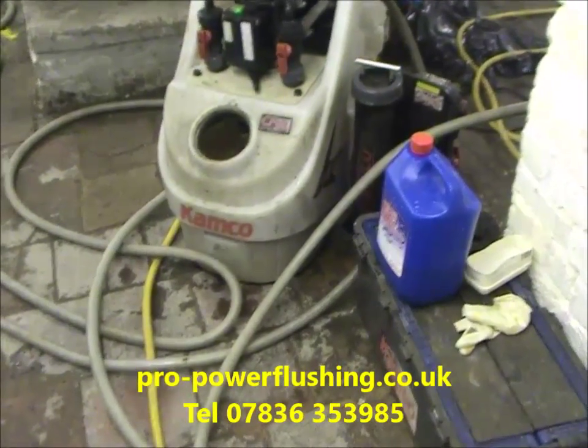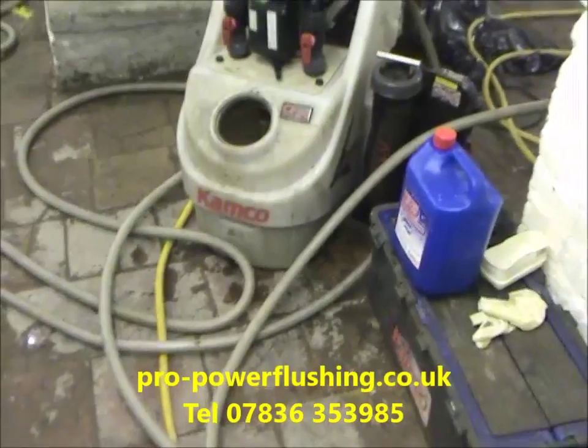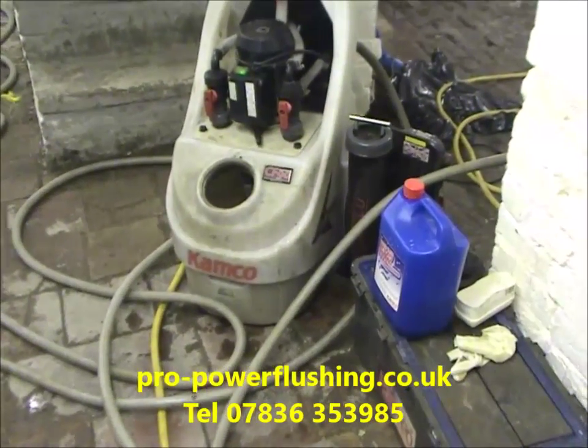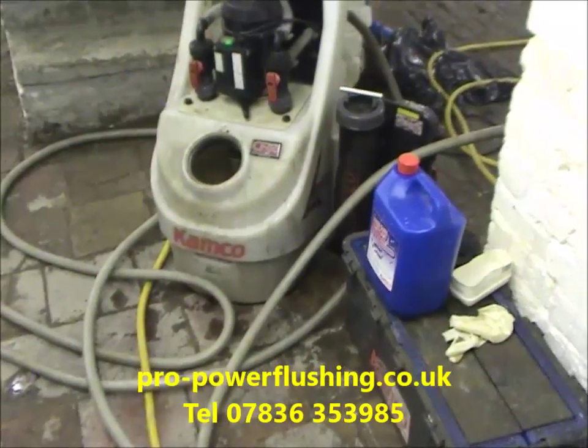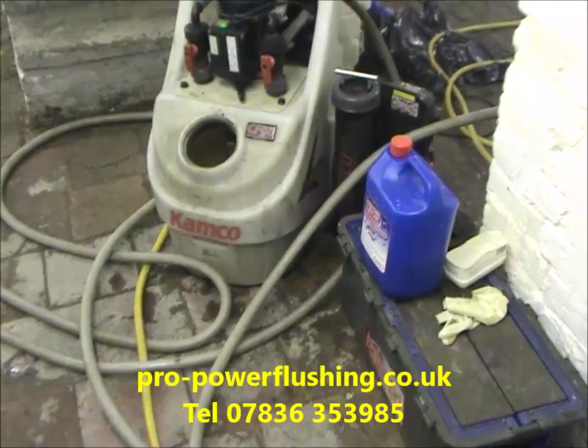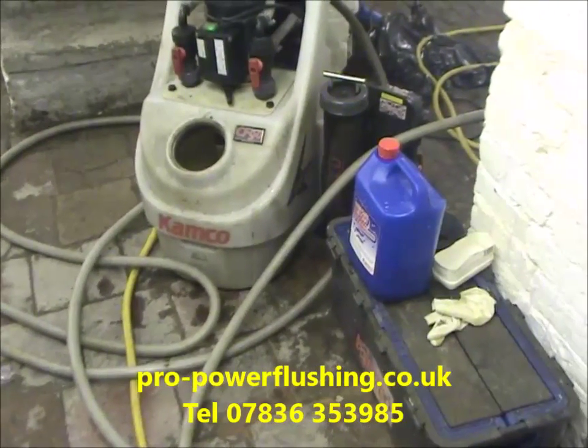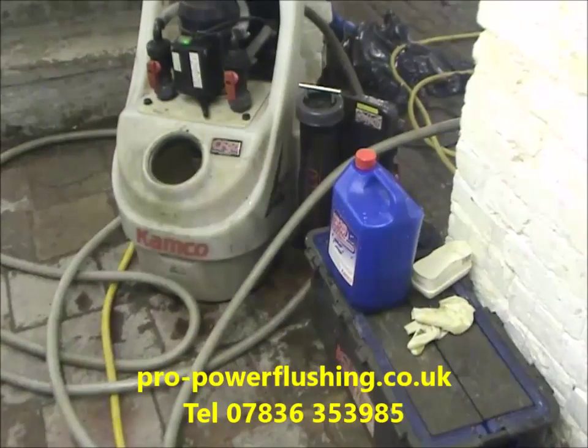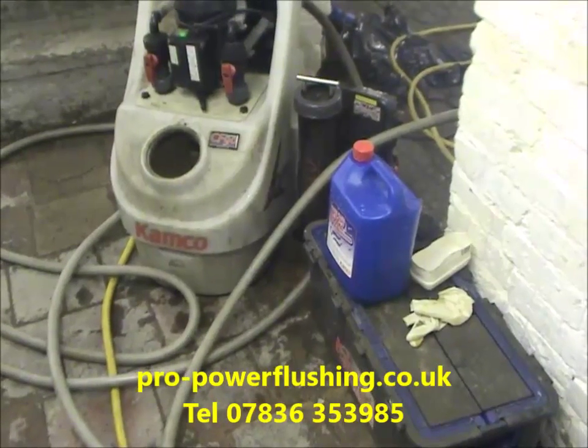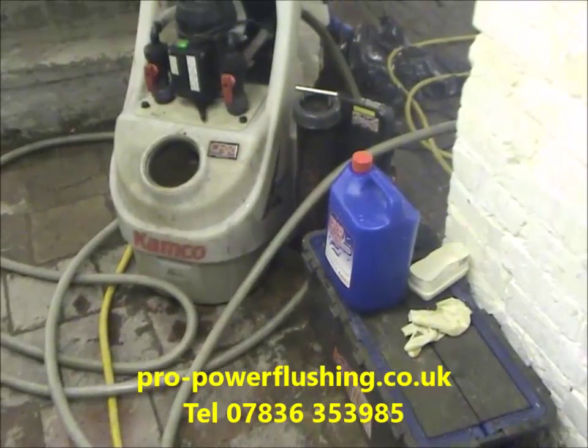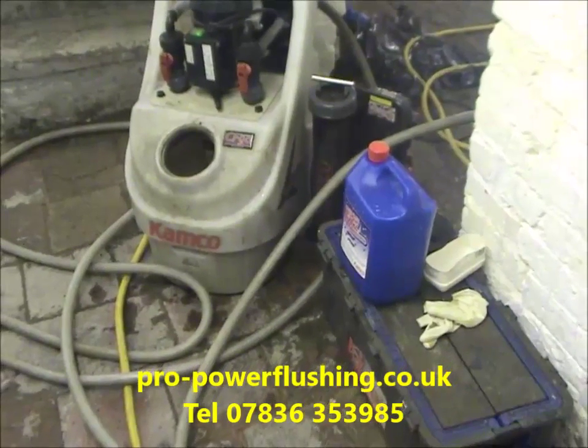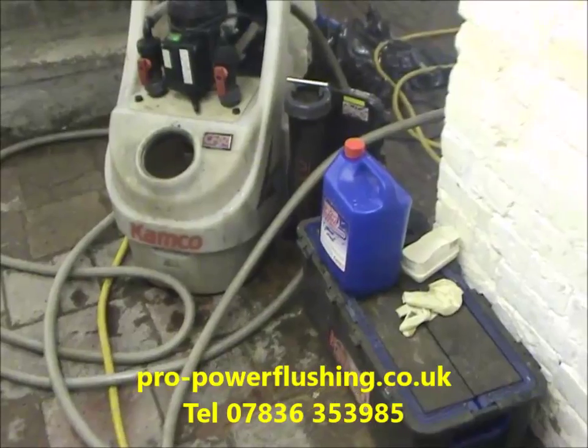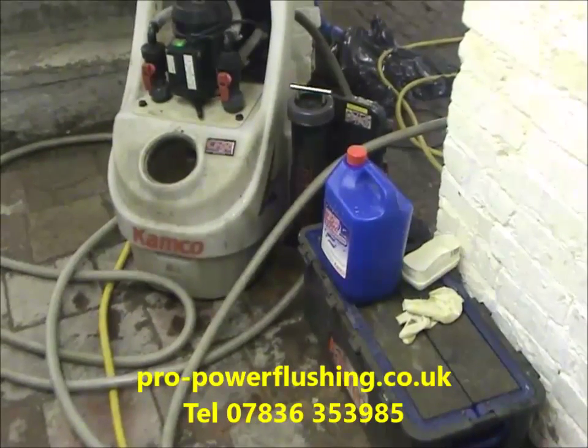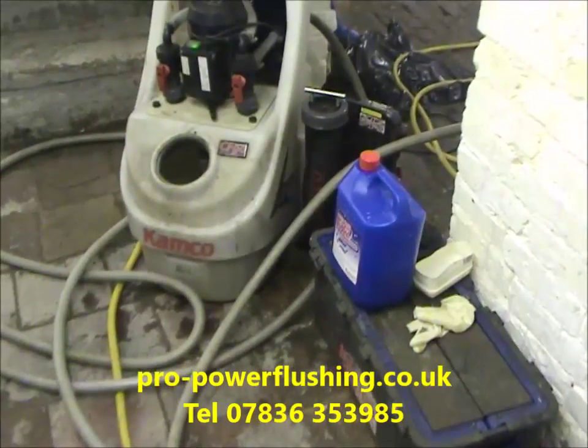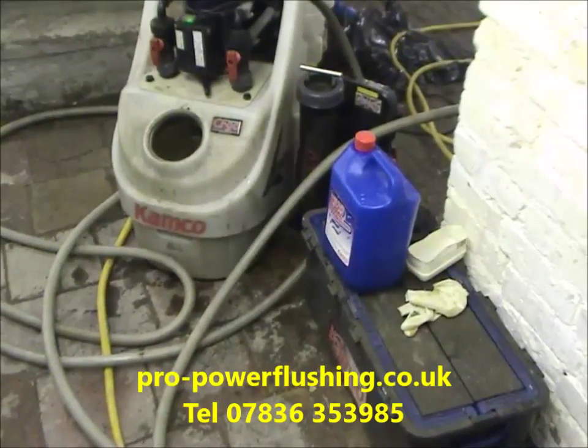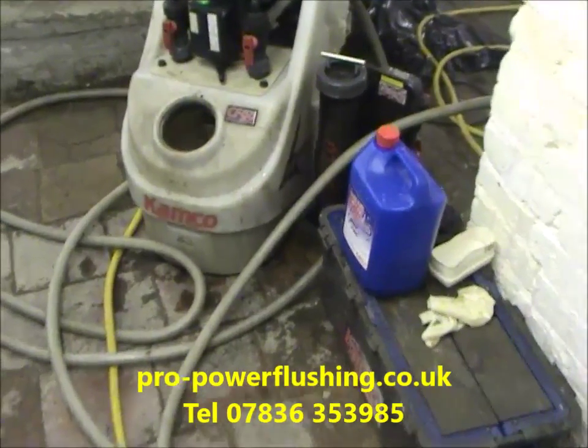Okay, so as we said before, my name is Barry of Pro-powerflushing. I'm a fully Gas Safe registered engineer, which is very important. If we're flushing combination boilers, we sometimes have to get into the boilers, take components off, such as gas valves and things, to get at things like plate heat exchangers. And if your powerflush company is not Gas Safe registered, basically they're not legally allowed to do things like that. So if you're considering a powerflush, make sure the powerflush company is Gas Safe registered if they have to get right into your boiler.